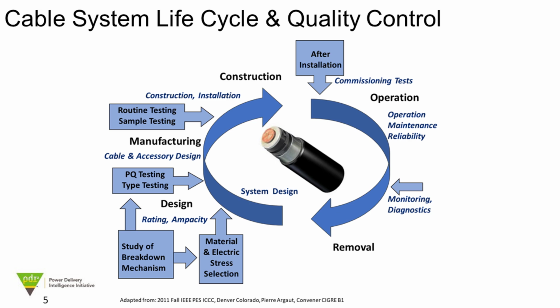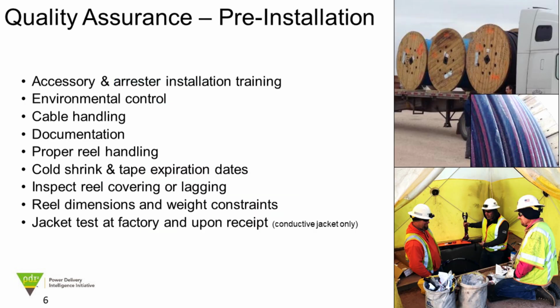I would say that not only is the final product tested electrically for overvoltage and partial discharge, but every component is also tested material-wise. This makes sure that what we get out in the field is exactly what was designed, and that includes the joints and terminations, which are the prefabricated joints and terminations that are the majority of what we use now on cross-linked or solid dielectric cables, and they are 100% tested in the factory. Every component manufactured in the factory is tested and sent intact to the field. That's where the next step, constructing the system, takes place.